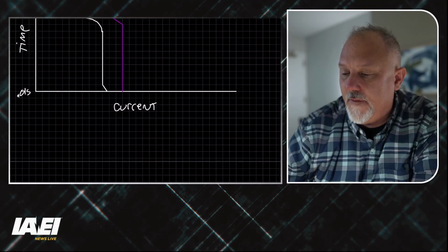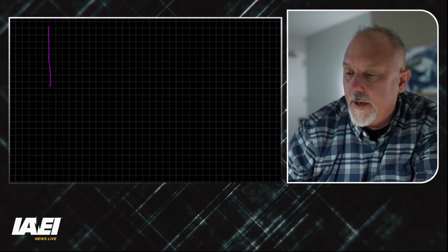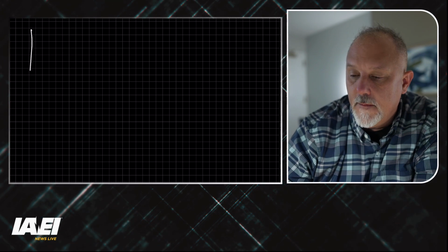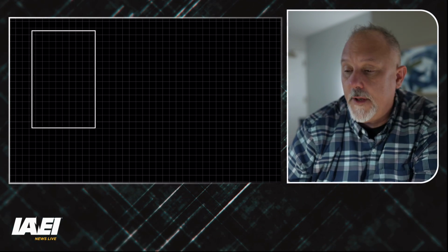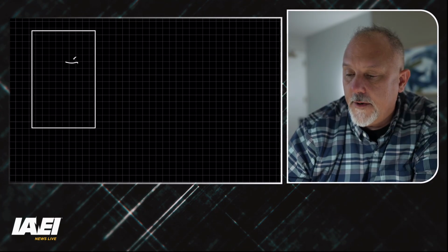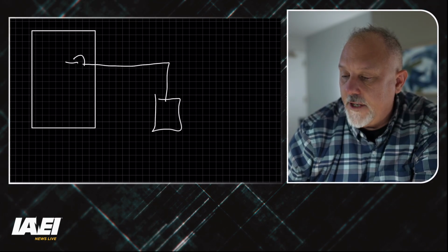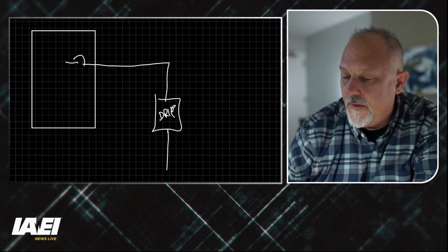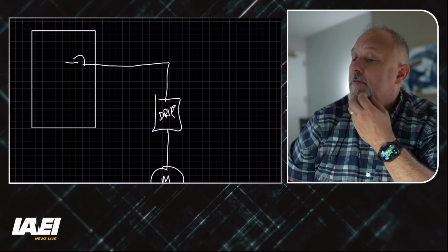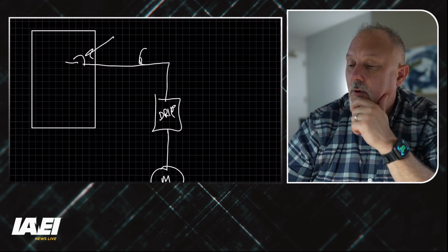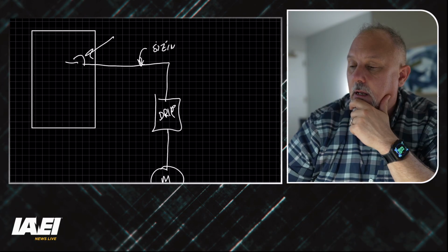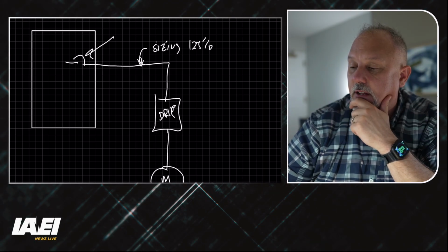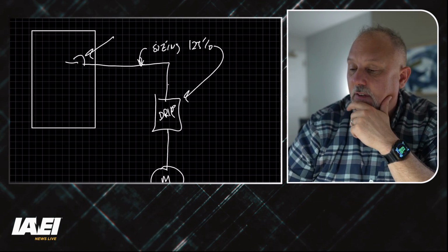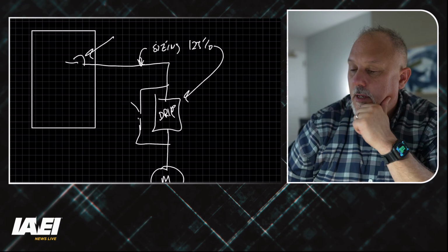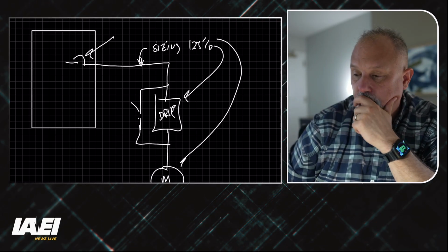Here's my issue. If I think about a motor circuit, I'm going to have a panel board, right? Isn't that a beautiful panel board? And I'm going to have a breaker in here feeding a drive. And on the output of the drive, I'm going to have a motor. We already know the sizing of this conductor is 125% of what's on that drive. And if I have a bypass, then I size it for that motor.